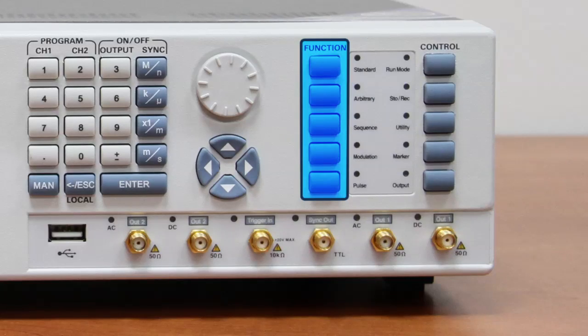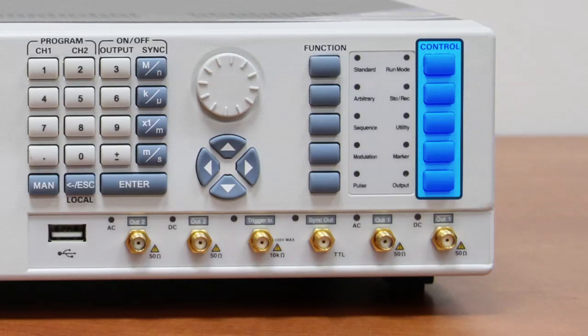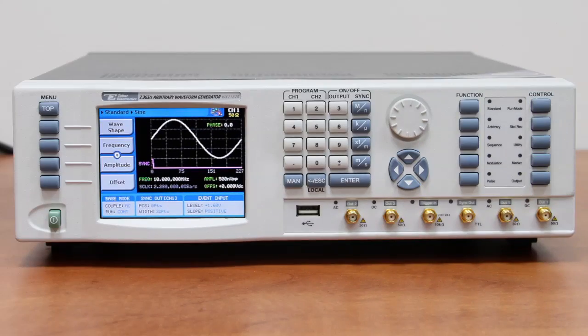On the right side of the front panel, we have the function menu keys. These select one of five function modes: standard, arbitrary, sequence, modulation, and pulse. These are the control menu keys. These select control menus that program the instrument operation. These are run mode, store/recall, utility, markers, and output.